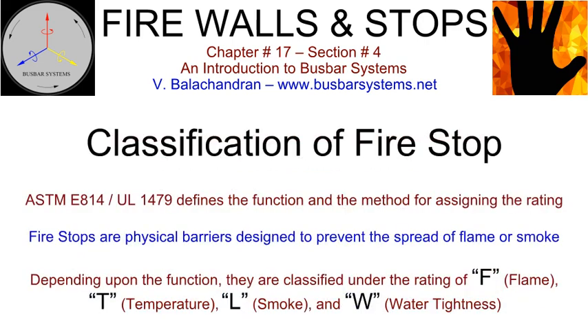Classification of fire stop. It is necessary to understand various classifications and the contexts in which they are used. ASTM 814/UL 1479 defines the function and the method for assigning the rating to a fire stop. Fire stops are physical barriers, designed to prevent the spread of flame or smoke. Depending upon the function, they are classified under F for flame, T for temperature, L for smoke, and W for water tightness. The letters stand for their withstand capabilities for flame, temperature, smoke, and water tightness.